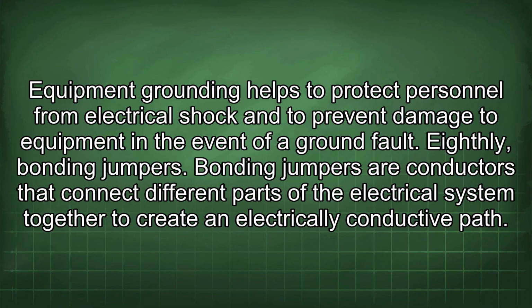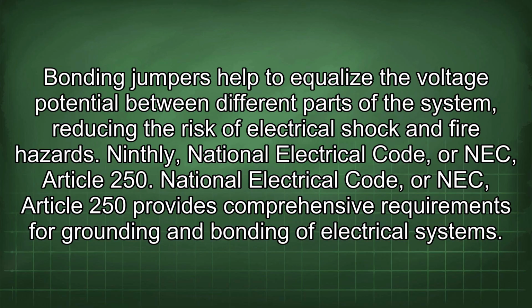Eighthly, bonding jumpers. Bonding jumpers are conductors that connect different parts of the electrical system together to create an electrically conductive path. Bonding jumpers help to equalize the voltage potential between different parts of the system, reducing the risk of electrical shock and fire hazards. Ninthly, National Electrical Code, or NEC, Article 250.